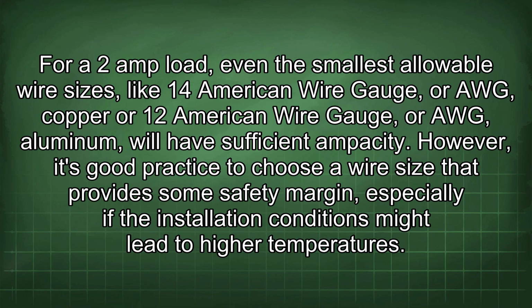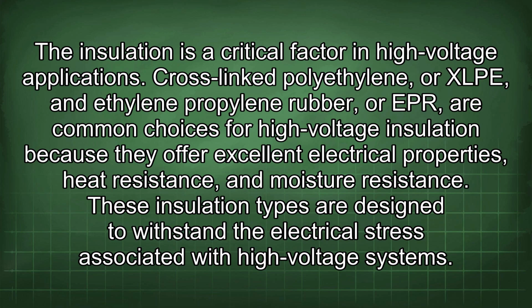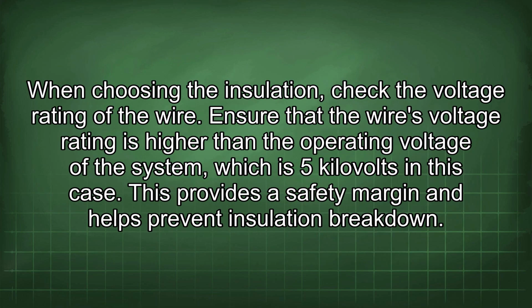lead to higher temperatures. The insulation is a critical factor in high voltage applications. Cross-linked polyethylene, or XLPE, and ethylene propylene rubber, or EPR, are common choices for high voltage insulation because they offer excellent electrical properties, heat resistance, and moisture resistance. These insulation types are designed to withstand the electrical stress associated with high voltage systems. When choosing the insulation, check the voltage rating of the wire. Ensure that the wire's voltage rating is higher than the operating voltage of the system, which is 5 kV in this case. This provides a safety margin and helps prevent insulation breakdown.